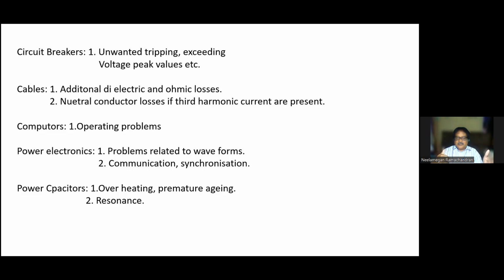He will just show us, see, 400, it will not trip. We have adjusted, nothing is going to happen. But once he steps outside the factory in 400, that circuit breaker will trip. Somewhere inside, harmonics will be playing a role. Cables, additional dielectric and ohmic losses will be there. Neutral conductor losses, operating problems, and power electronics problems related to waveforms, communication, synchronization, power capacitor overheating, premature aging, resonance. These are all the problems of harmonics.